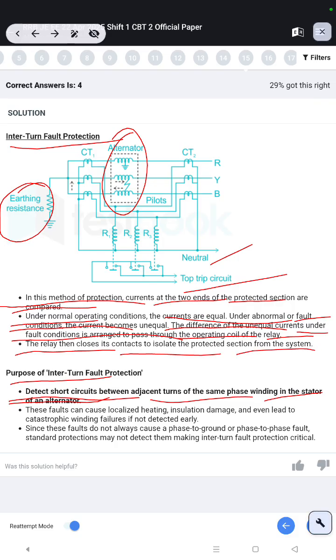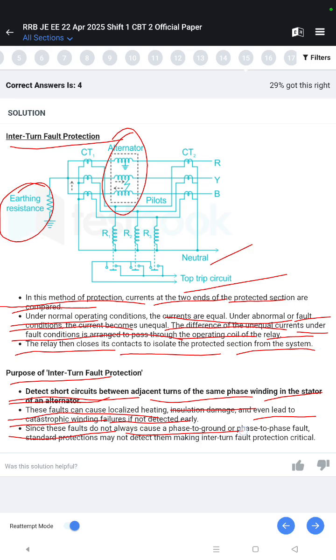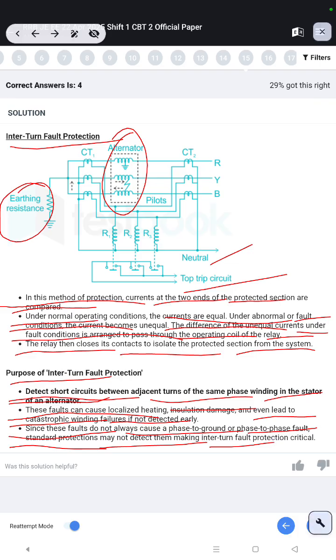This fault can cause localized heating, insulation damage, and even lead to catastrophic winding failure if not detected early. Since these faults do not always cause phase-to-ground or phase-to-phase faults, standard protection may not detect them, making interturn fault protection critical.